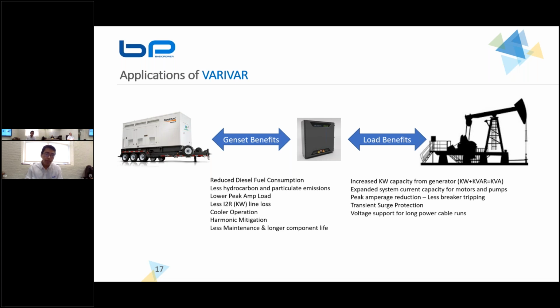Now, the load benefit is that you will have an increased capacity, like we mentioned before, and you'll have fewer breaker trips because a lot of the times, if you have a lot of current running through your system because of poor power factor, you might run into nuisance tripping. Harmonic distortion can also cause nuisance tripping. So your equipment might suddenly stop working during the operation, and that might cause a lot of downtime as well. And we can also provide transient surge protection and voltage support to make sure that your operation runs smoothly, right? When surges come in through your generator, we want to ensure that it doesn't impact the operation itself and everything continues to run as intended.